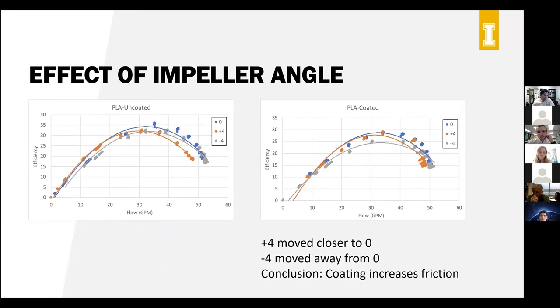This 0 is as is, similar to the stock impeller, and then orange is +4 and the gray is -4. If you just focus on this area, it becomes clear that at this point, +4 and -4 have about the same efficiency, which is lower than the 0 angle. And if the coating had reduced the friction, then the orange impeller, which is +4, would have lower efficiency when it is coated. And the gray one, since that is -4, that's the model impeller, when coated, if it had lower friction, it would move closer to the blue one.